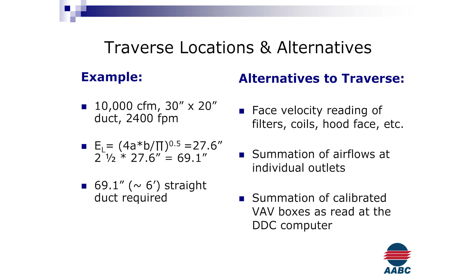Obviously, this has occurred after the VAVs have been calibrated and checked out. But if you have them all set up at max, you're simulating a full cooling load on the building, you can look at what all the VAVs are doing in the absence of a traverse and hopefully back into what the total flow of the fan is, if we can't achieve that reading for you.